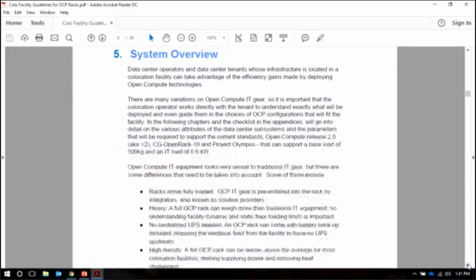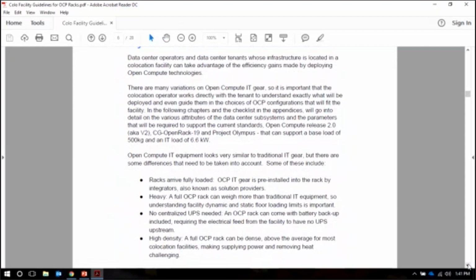The document is intended for an operator who doesn't know much about open compute. If a customer said, hey, I want to deploy an open compute rack in your colocation, what does that really mean? Is it different from regular IT gear? The general differences are that the racks arrive pre-integrated and fully loaded—not an empty rack you populate on site. It could be a full rack of IT gear, so there are considerations around the loading dock, the pathway to the data center, and the floor loading of the data center.